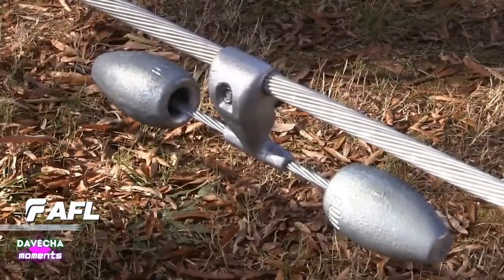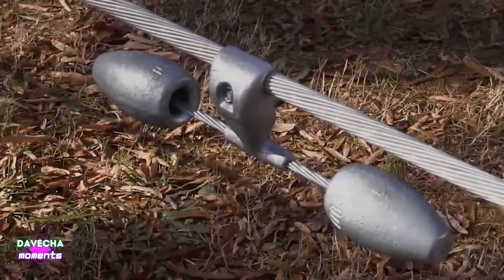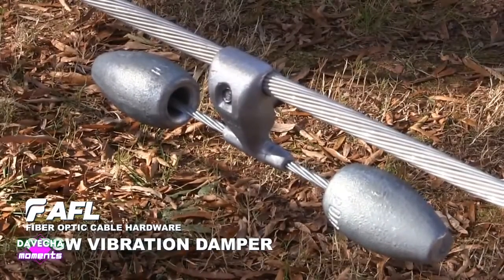And therefore, what is done? We have Stockbridge dampers that help to reduce this oscillation so that the oscillation cannot damage conductors. Stockbridge dampers are connected, let's say power is coming from this side, before it is connected to insulators to connect to pylons. We have Stockbridge dampers, and then insulation, and then the tower, and then on the other side we have insulation, and then Stockbridge dampers as it continues. They are connected one-one, or even at times two-two. So that is what is done about the Stockbridge dampers.